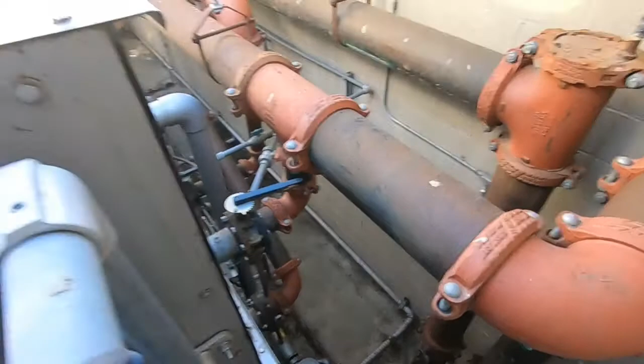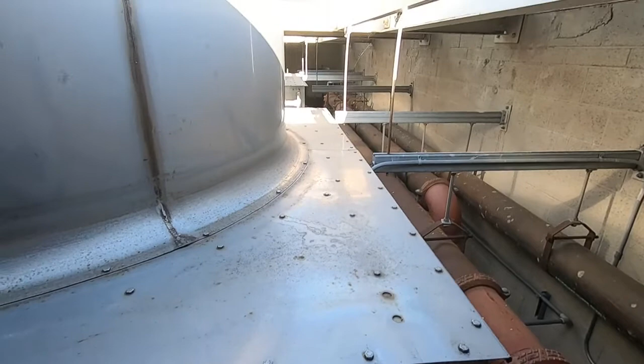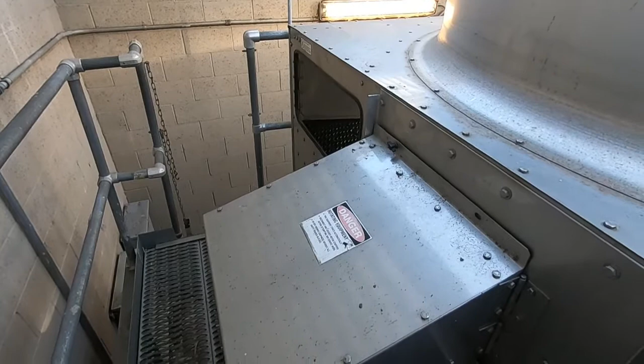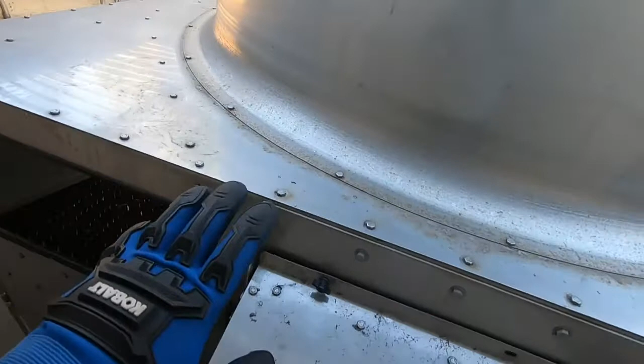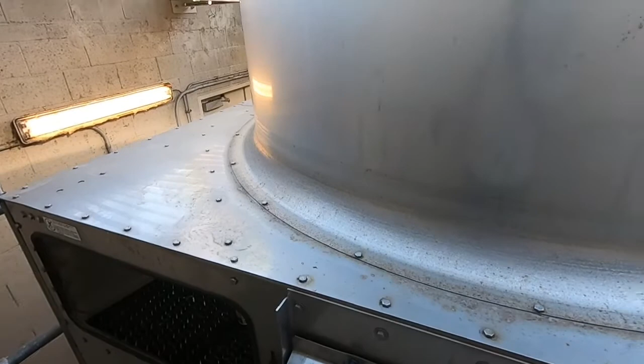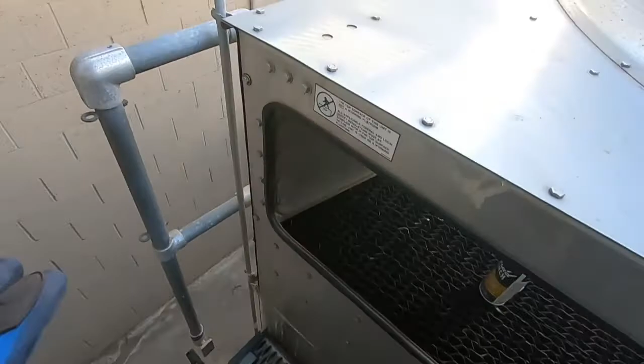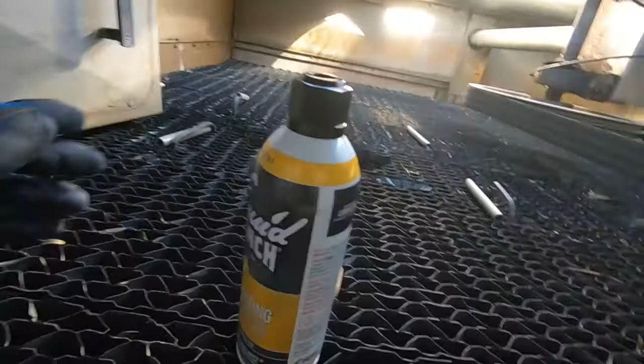Right now we're kind of lucky, because lately it's fall, so in California it's getting cooler, but randomly we're getting these two days of heat—today's 90 degrees, tomorrow's supposed to be about 94. So instead of running the fan and risking it shaking itself to death or something happening to the fan blade, I've got the fan completely off but the pump still working. That's what you can probably hear—we're still using the pump for water, to help with some heat exchange on the cooling load. So we've got the sprays working here, and the other cooling tower next door has sprays and fan running, which should get us through the day until we get this one changed out.